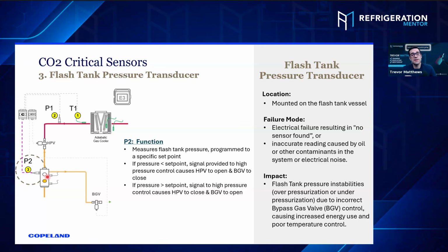Yeah. And that's really important because this valve here is probably one of the most important. I used to think it was the high pressure valve, but the flash gas bypass valve is probably one of the more important ones, because the ambient outside doesn't really change a lot, unless you're in Calgary, Alberta, and it's 20 today and minus 20 at night. But yeah, you're right. The ambient kind of stays the same, whereas now the dynamics of all the different things, if you have hot gas defrost, if you have cases calling, that valve is doing a lot of work. So it's so important to make sure that that transducer is running right. Absolutely, because that valve has a big impact on your system efficiency. Because if you can get up to 50% of your mass flow in the middle of the summer flowing through that valve, you don't want any more mass flow than you need going through that valve, because that just means energy and efficiency loss. So that's for sure.